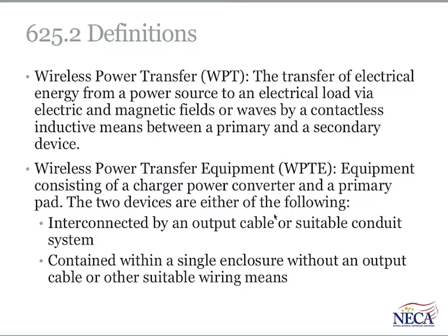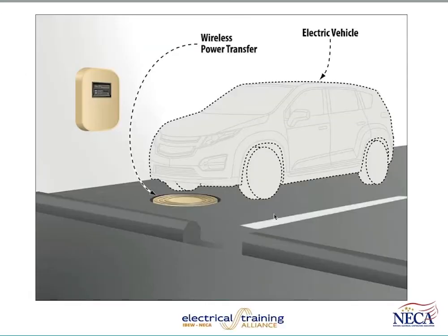So two new definitions of wireless power transfer to tell the user of the code what that is. Basically, there's no contact with wire between the vehicle and the supply equipment. And then the electric vehicle supply equipment, it's wireless power transfer equipment, consisting of a charger, power converter, primary pad, and the two devices that are either of the following: interconnected by an output cable or suitable conduit system, or contained within a single enclosure without an output cable or other suitable wiring means. But what we're looking at is the ability to transfer power wirelessly through a magnetic couple.